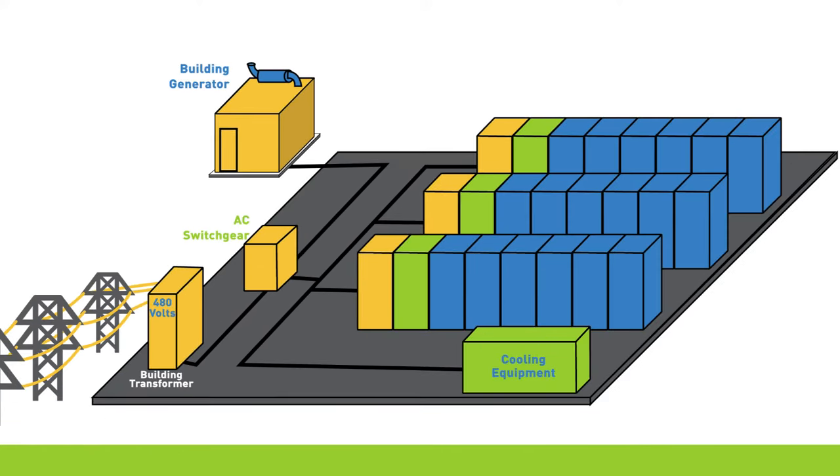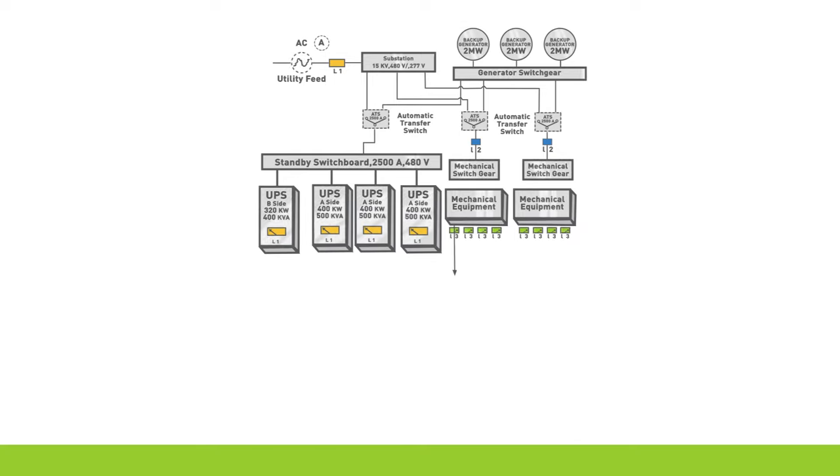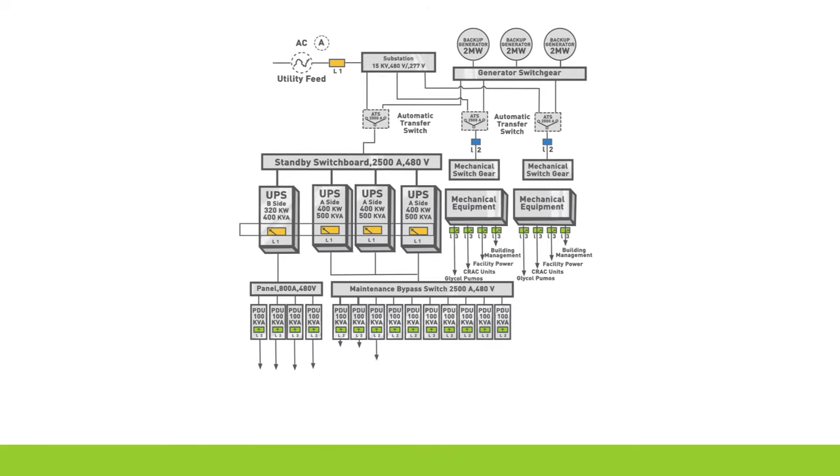Many power disruptions can be under 3 seconds, so a data center operator will not want the generators turning on needlessly. Also, it takes a little bit of time for the generators to completely power up and reach a stable level of power output. To bridge the gap between when the utility power stops to when the generators are delivering full power, we have a standby power source called an uninterruptible power supply, which is known as UPS.